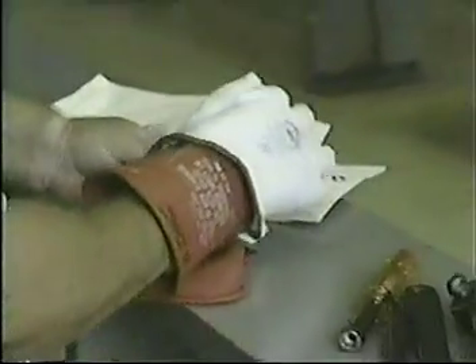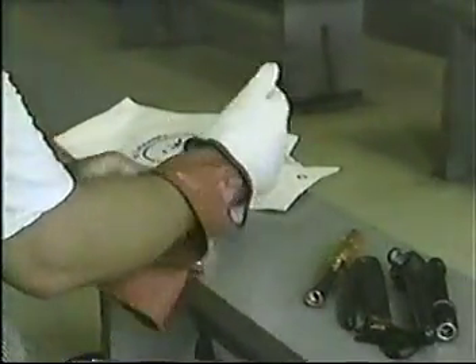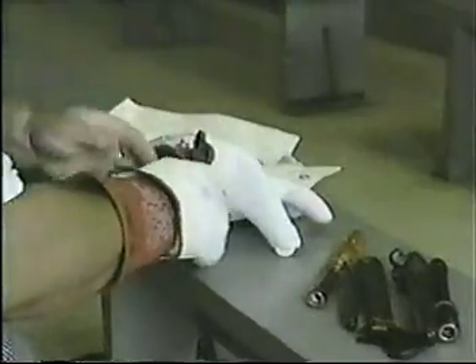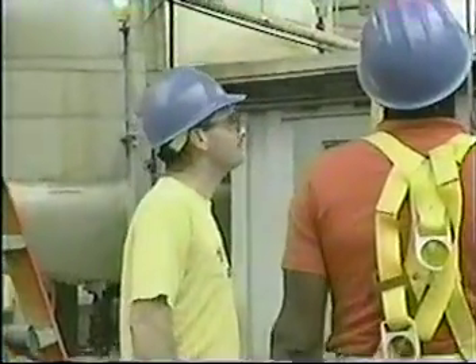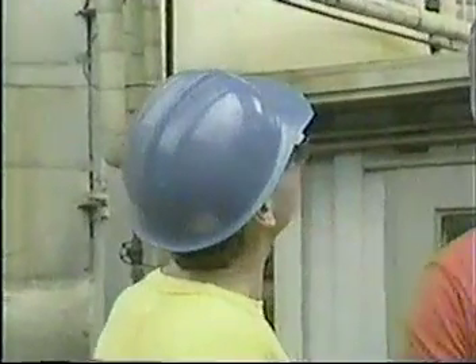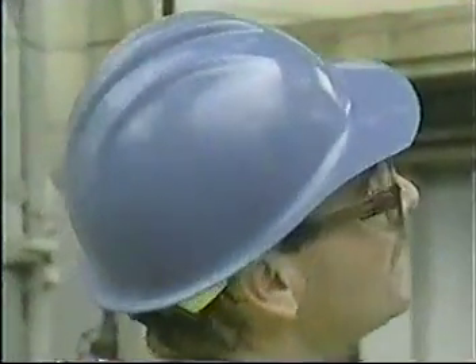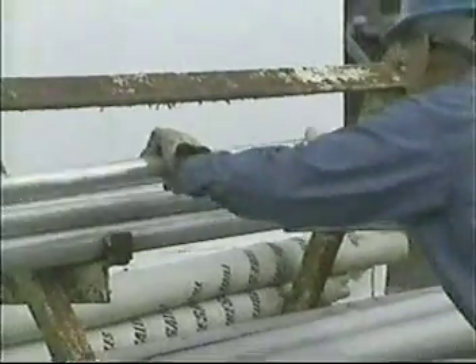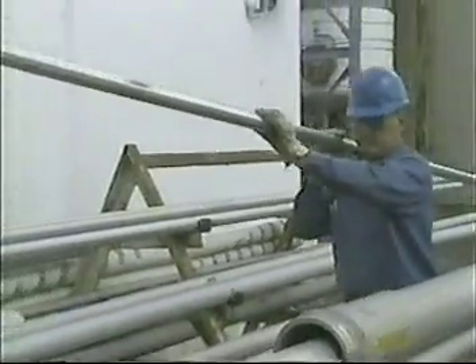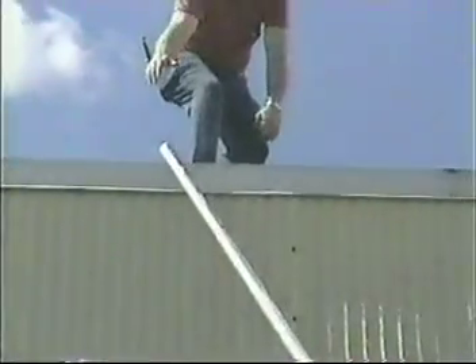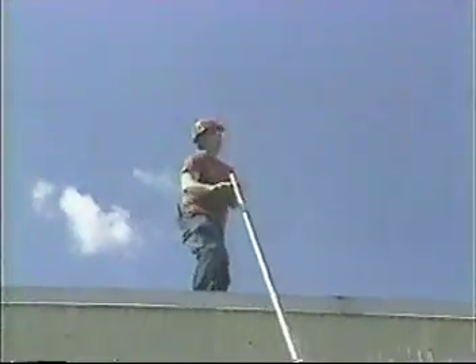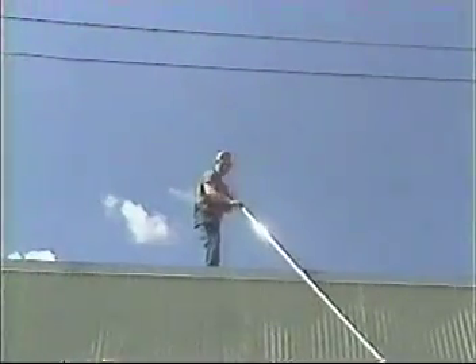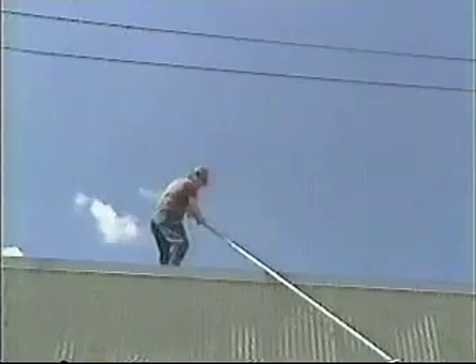The chance of inadvertent contact can be reduced by the use of protective equipment, such as properly rated and tested insulating gloves and non-conductive hard hats. If protective equipment is called for, use it every time. The key to preventing accidental contact is to be alert to your surroundings. Don't get yourself into a situation where you or any object you are touching can contact or even come close to an energized conductor. Be especially cautious if you encounter conditions where it is necessary to place your hands or tools in a position that is difficult to observe.